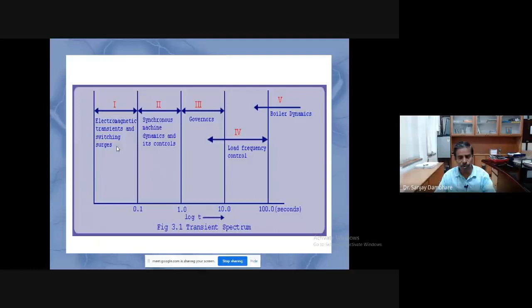So the protection time is relay time plus circuit breaker time, and the protection time is less than even one cycle. So that is the hard constraint, because the circuit breaker is a switch, and in the circuit breaker you have to physically interrupt the circuit, so the current is to be interrupted in the circuit breaker, and it is a mechanically operated switch, and that's why its operation will be a little bit sluggish. So it will take more time to operate than the relay.